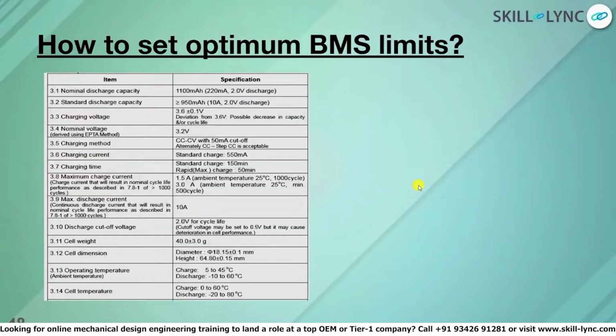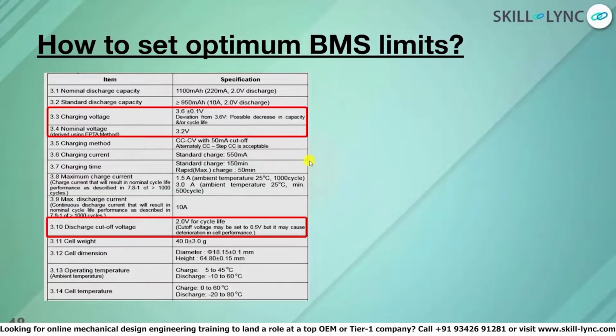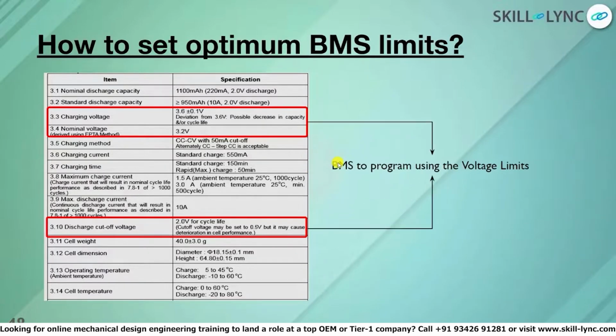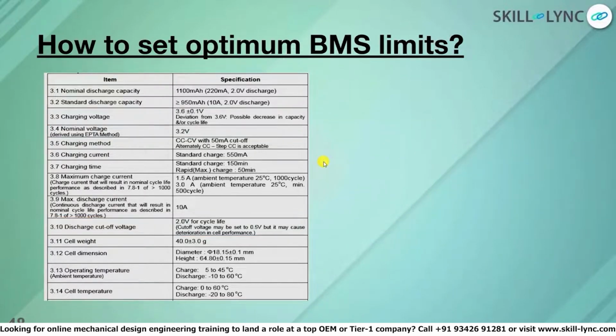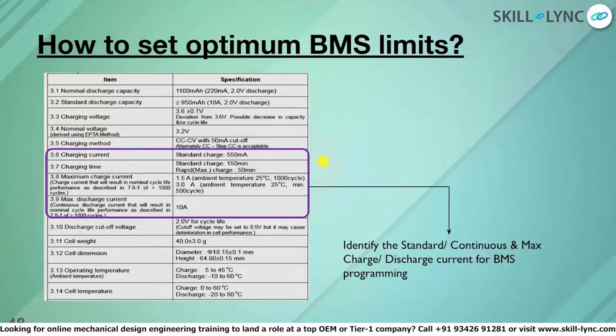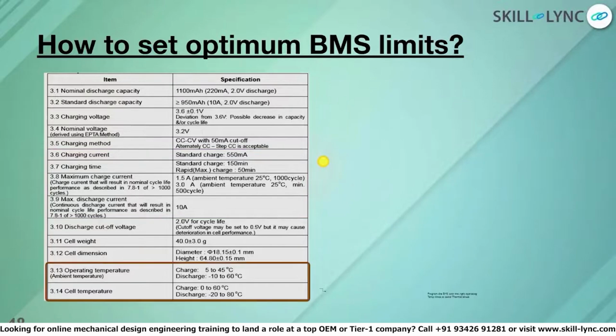So how do we set those BMS limits? Now we have red windows, which is charging voltage and discharge cutoff voltage - certain voltages which we program in the BMS. Then we have overcharge and over discharge current C rates, which are responsible for the continuous C rate, continuous discharge rate, maximum C rate, and maximum discharge rate.